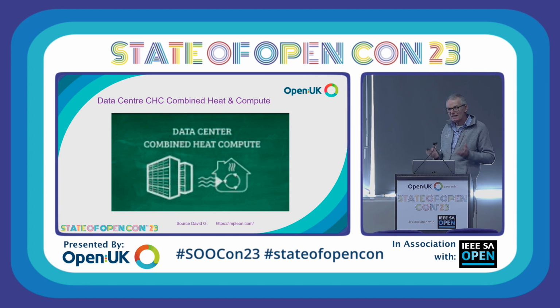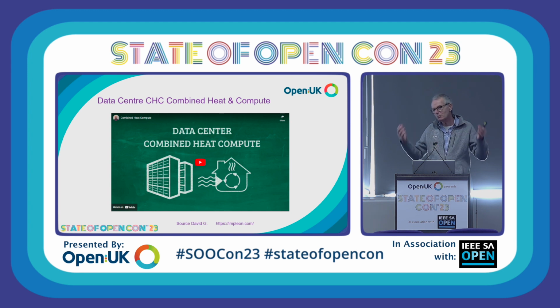Now, you can do things better. Things can be done better. If we look at heat reuse from data centres, because these data centres generate megawatts of heat, hundreds of megawatts of heat, some of them - this is just to try and get you into the idea of breaking down these silos. Something Eric mentioned yesterday, talking about breaking down the silos between software people and hardware people. But what I'm saying is you need to break down the silos between utilities. Why are we using gas to warm up water when we've got all this heat from a data center using green electricity, which we can then use to replace burning gas?